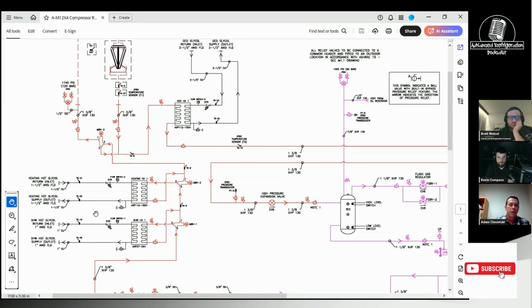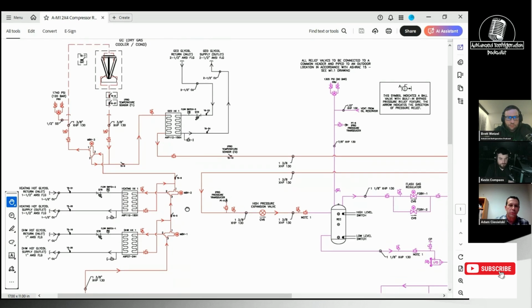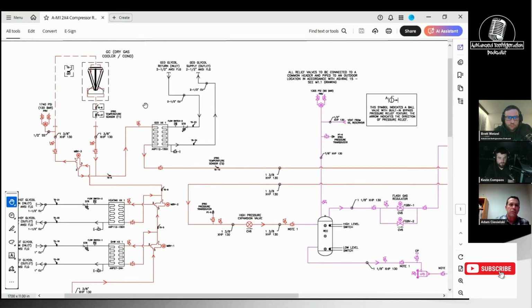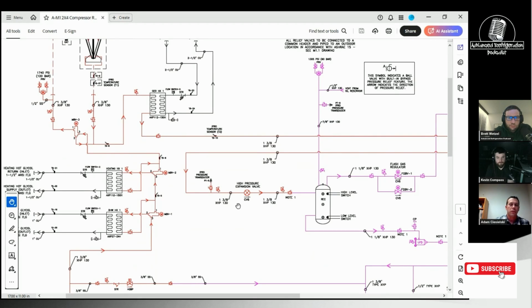At first, we do not modify anything from the rack perspective. If we can produce the heat without artificially raising the head pressure or the gas cooler temperature, we try to do so. So first stage basically is we modulate these valves. If in fact we're not meeting the set point and this valve is at 100%, then we'll start raising the gas cooler outlet temperature by raising the set point of the fans, the drop leg temperature, which reduces the fan, raises the drop leg temperature, and then artificially then with the high pressure expansion valve can raise the discharge pressure up to the valve. That enables us to produce more heat.